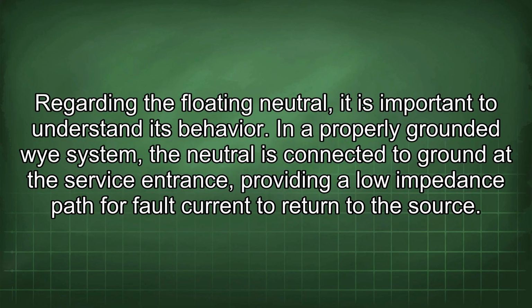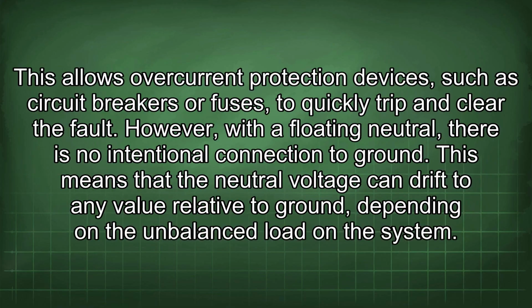Regarding the floating neutral, it is important to understand its behavior. In a properly grounded Y system, the neutral is connected to ground at the service entrance, providing a low impedance path for fault current to return to the source. This allows overcurrent protection devices, such as circuit breakers or fuses, to quickly trip and clear the fault.